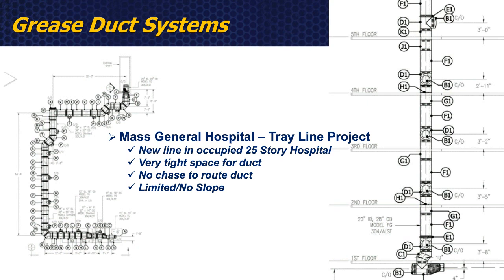We had a very tight space to fit this ductwork in, and there was no place to do a fire-rated chase to route the ductwork. So we would need to find an area in the building we could route this straight up to get the fumes of the hood out of the building. So we also had very limited ability to slope this system. I'm going to show you some pictures of installation, but basically the grease duct ended up having to be flat oval and sandwiched right up against the ceiling of the kitchen area.